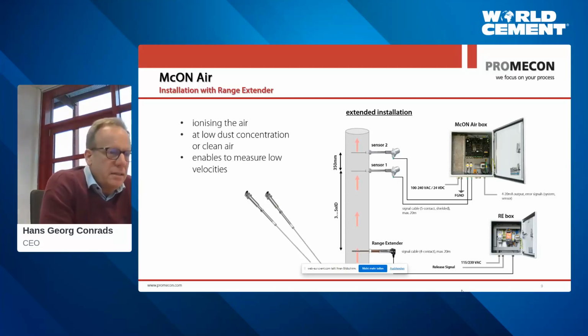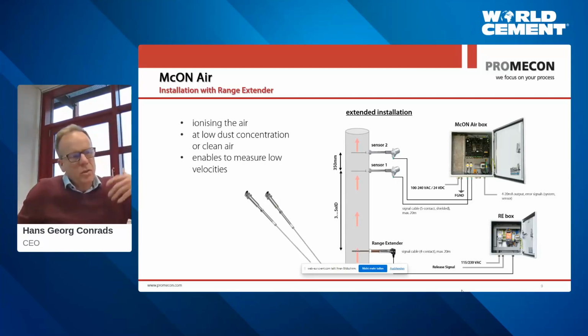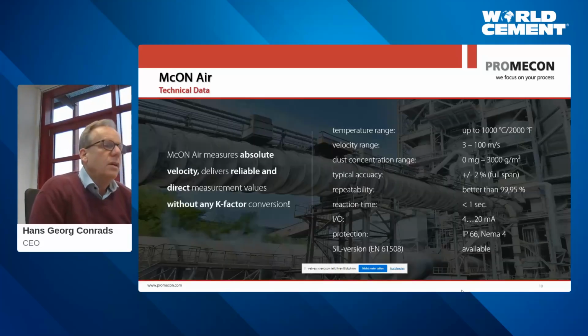In cement plants, usually there is no need for a range extender, because in a cement plant, usually the gas is so dusty that it's always easy to measure. And there is no condition where you have really clean gas. When you are measuring the dedusting system of a copper plant or a steel plant, you sometimes have fairly clean air, and then you have very dusty air. So for this, we have this range extender, but I guess in a cement plant, it's not such a big demand for it. So what can we say about the measurement?